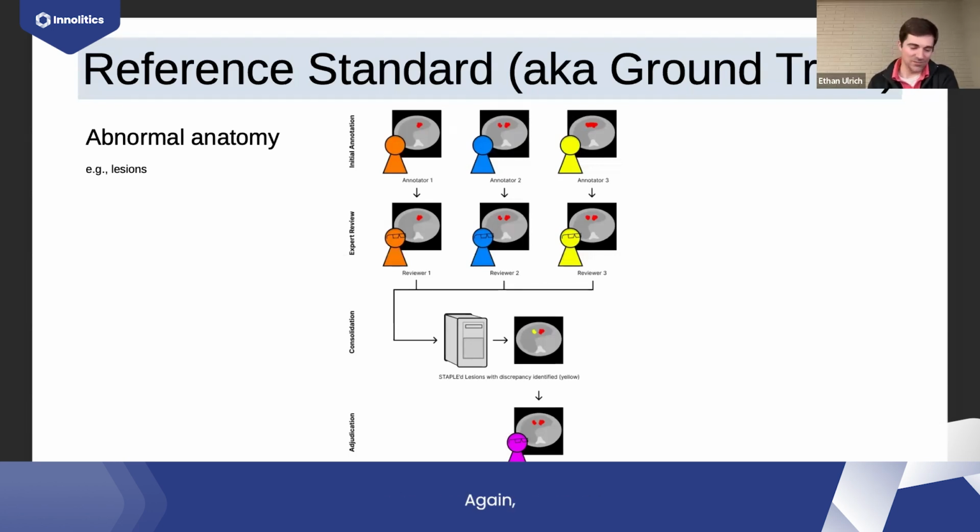Hey, yeah, that's definitely not a good place to be in. For that situation, again, a pre-sub with the FDA to explain it to them is definitely needed. Like for the situation with brains of pediatric patients, not a lot of radiologists are qualified to do segmentations on those brains. You typically want a neuroradiologist, someone that's specific to the brain, to do that. So we kind of ran into that. They definitely wanted neuroradiologists to be the reviewers. So we had to find those, and that wasn't very easy. But yeah, I'm not sure is my answer.